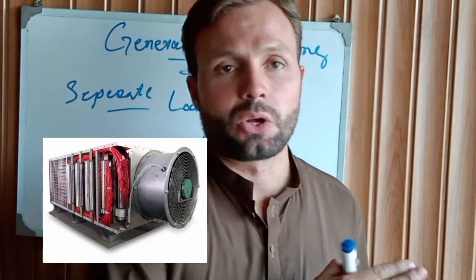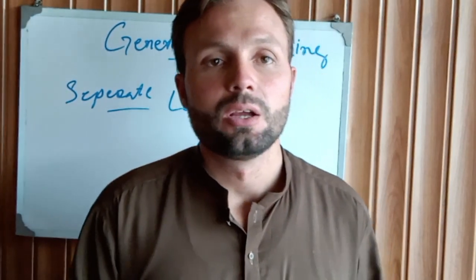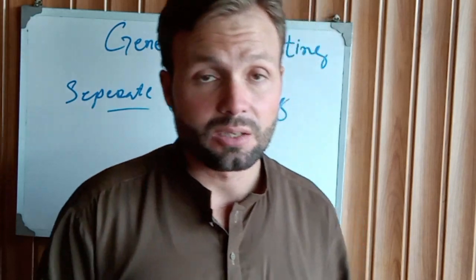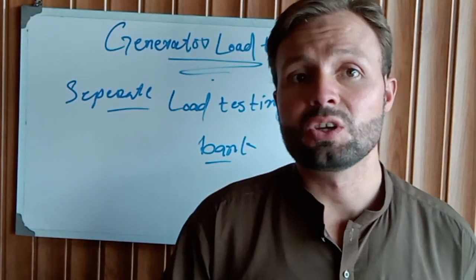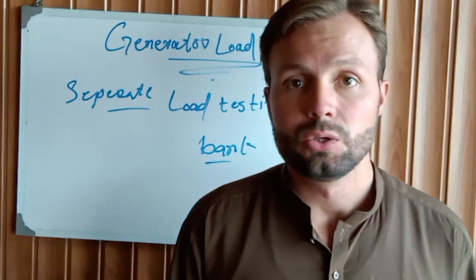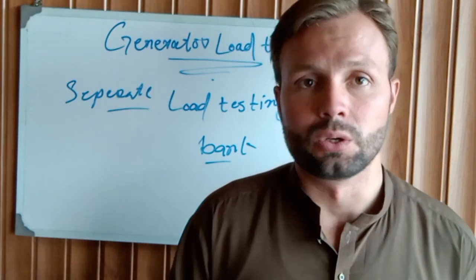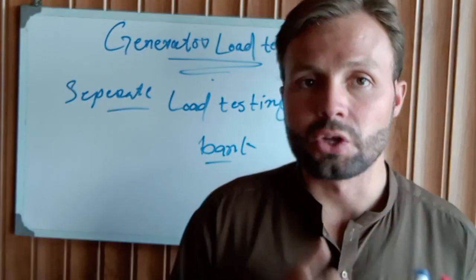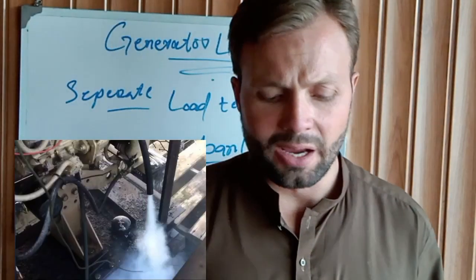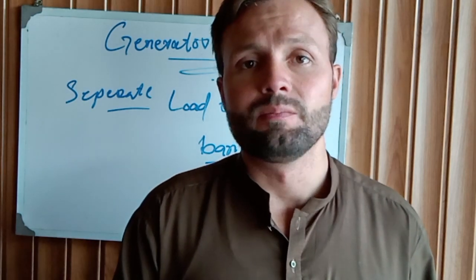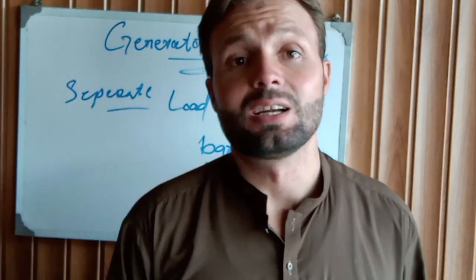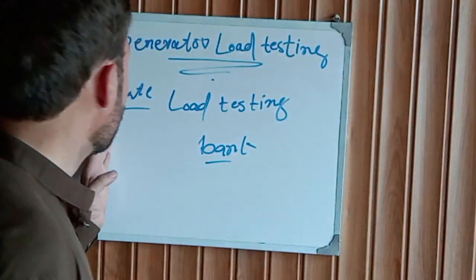The best method for generator load testing is a separate load testing device called a load bank. This load bank has a lot of heater coils, and each separate coil has separate buttons for turning on and off. For example, if you have a 15 kilowatt generator and you want to check how much load it can actually carry, you need to put load on it to check for blow-by, misfire, vibration, heating, and smoke or dirty emissions.